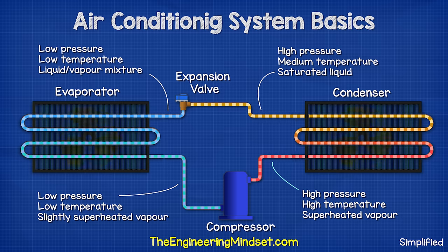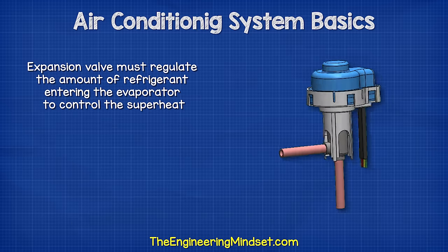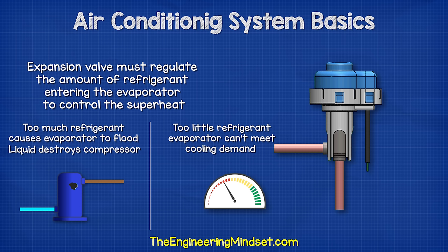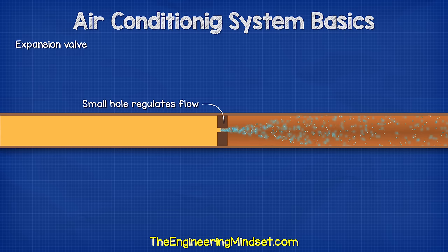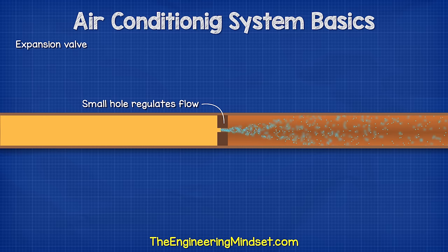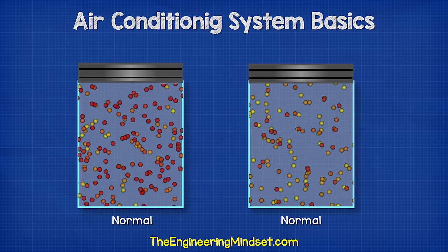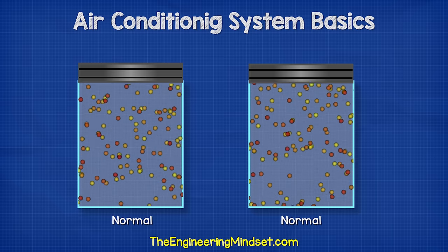The refrigerant therefore exits as a high pressure, medium temperature, saturated liquid, and this heads to the expansion valve. The expansion valve needs to regulate the amount of refrigerant entering the evaporator to control the superheat. If it allows too much refrigerant to flow, it can flood the evaporator, so the refrigerant doesn't evaporate and liquid reaches the compressor and possibly destroys it. But if it lets in too little refrigerant, the system won't provide enough cooling, and so it operates inefficiently. The expansion valve regulates the refrigerant by only allowing it to pass through a small hole. This creates a large pressure difference across the valve — one side is the high pressure liquid, the other side is almost empty. The small hole causes it to almost spray into the evaporator as a part liquid, part vapour mixture. The refrigerant will expand to try and fill the empty space on the other side, and this will cause it to drop in pressure as well as temperature.